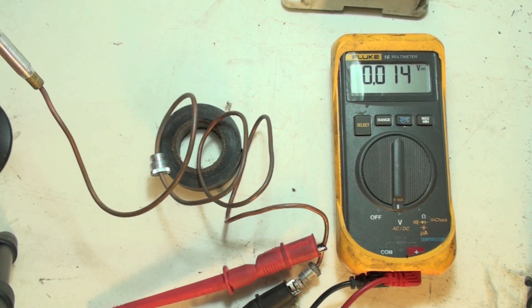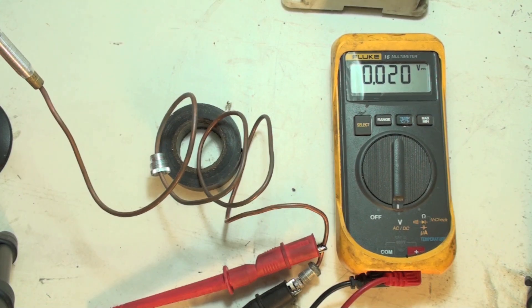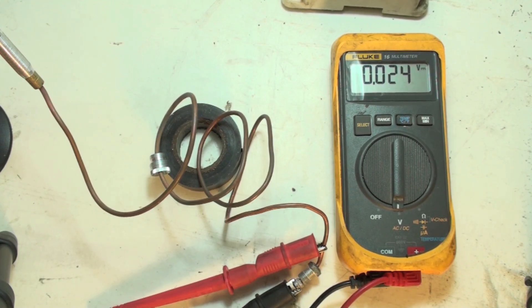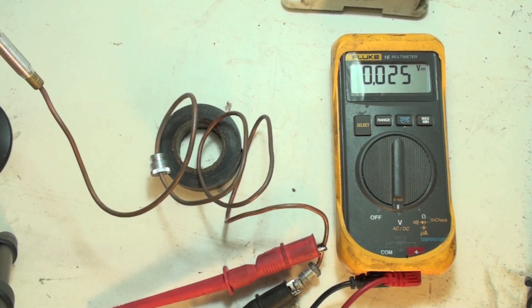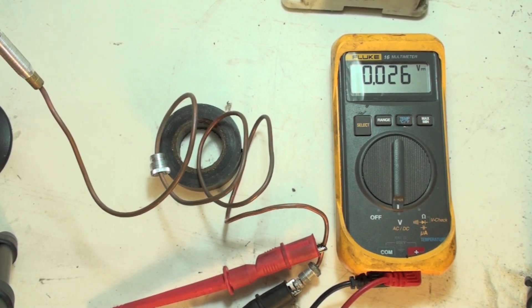Most of these things will drop out at 10 millivolts. They should operate at—we generally figure 18 to 22. Now using a torch like I have here is pretty intense heat and it'll probably bring it up above the 22 by quite a bit. Normally you would test these things actually inside the furnace using the pilot light that's available.